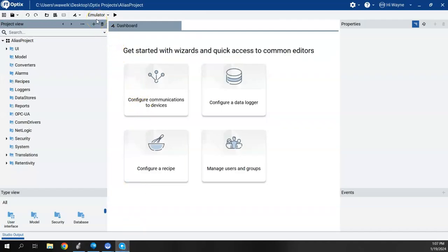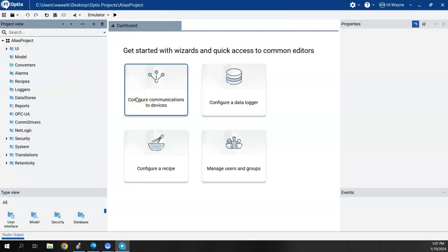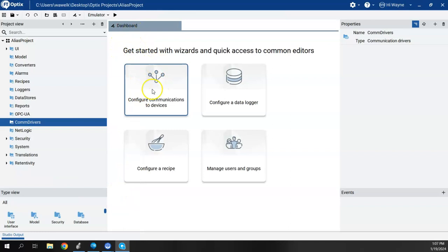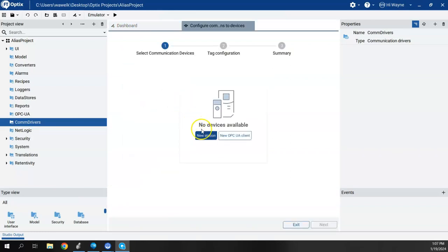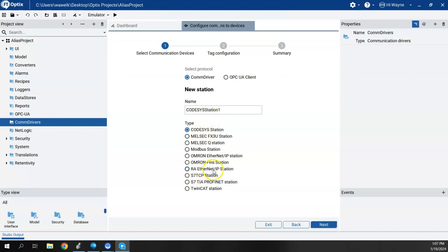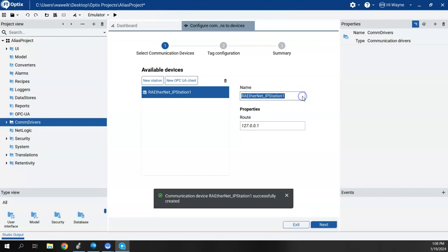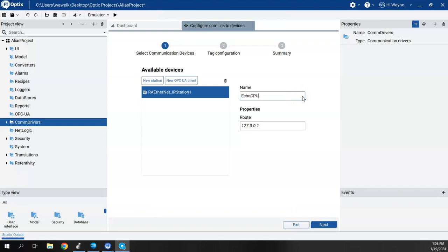We're in a blank Optix project with nothing pre-configured. The first thing we'll do is configure communications to the Logix controller. I can right-click on CommDrivers and select New, then choose RA for Rockwell Automation EtherNet/IP driver. I'll use the wizard from the dashboard: select New Station, choose RA EtherNet/IP Station, then enter the IP address of my Logix Echo emulator. I'll name it Echo CPU.